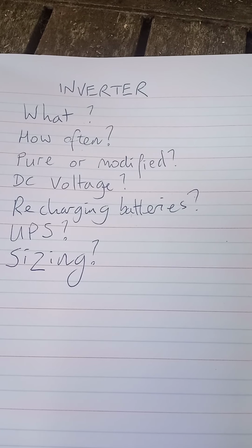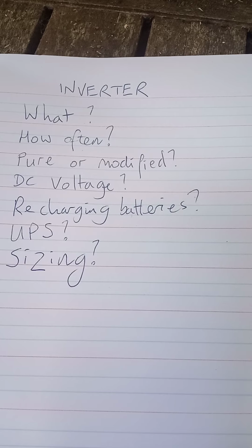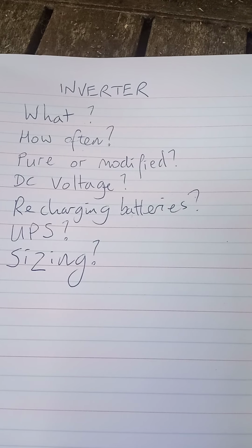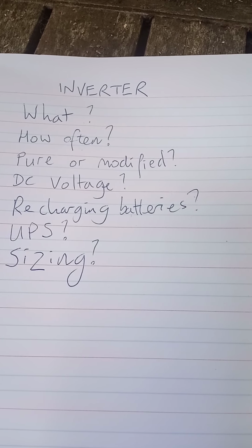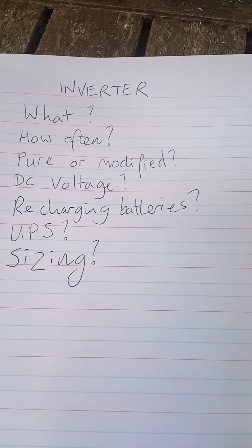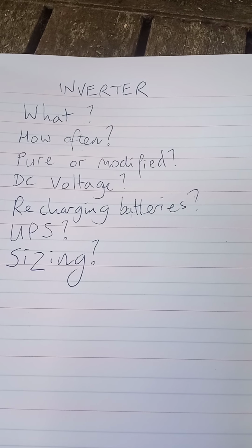What's driving that is the size of the cabling for the inverter, which is quite a big subject on its own. Basically, you have very high currents traveling through the DC positive and negative cable from the battery bank to the inverter, and the bigger the DC voltage, the smaller the cable needs to be.